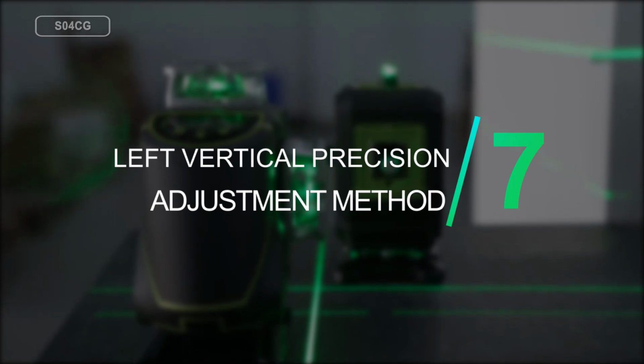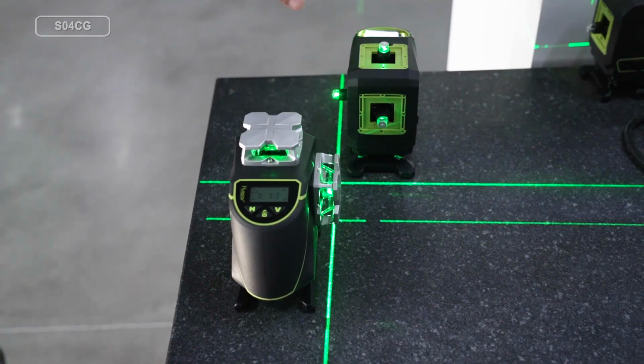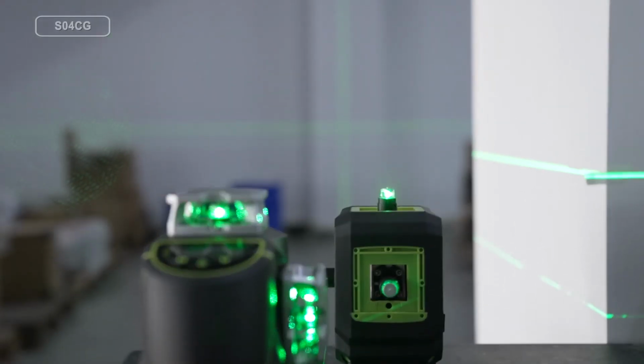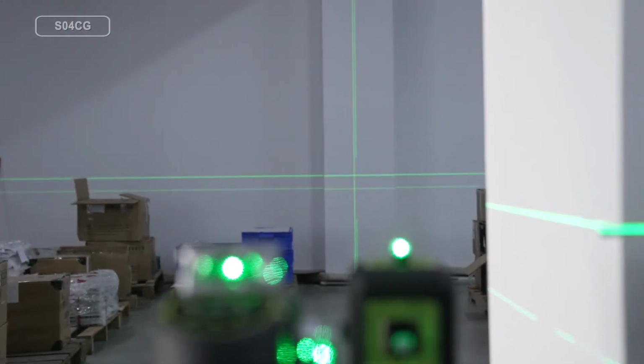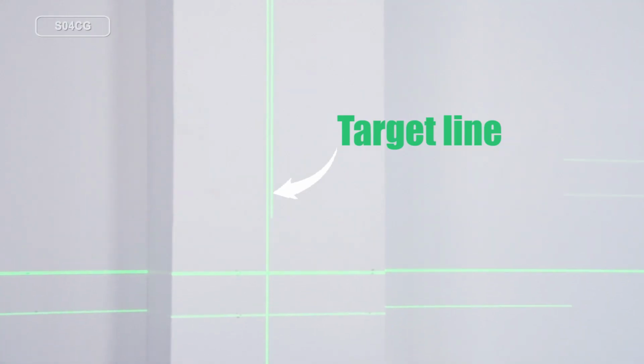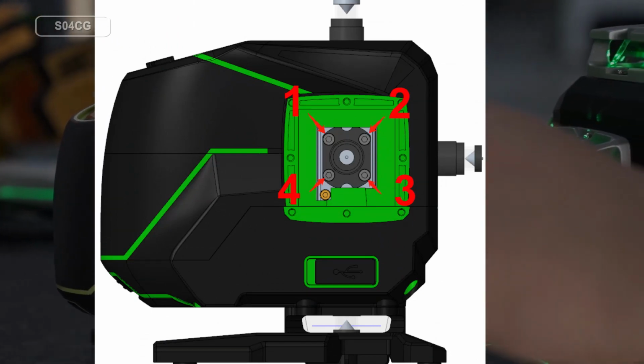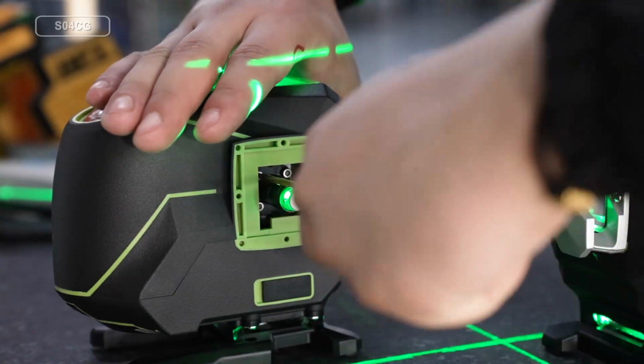Left vertical precision adjustment method. Align the left vertical line with the standard prototype. Check the top and side wall connection coincidence. Compare the difference and adjust the screw position of the reference line.